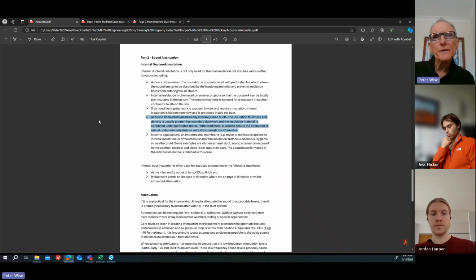If you use perforated foil, it will tend to erode over time. It doesn't have much strength. Under normal low velocities, up to 8 or 10 meters a second, it's going to be okay. But when you're getting up to the high velocities, it will tend to deteriorate over time, and you don't want that to happen inside an attenuator because it's not really accessible to repair it if you have to.